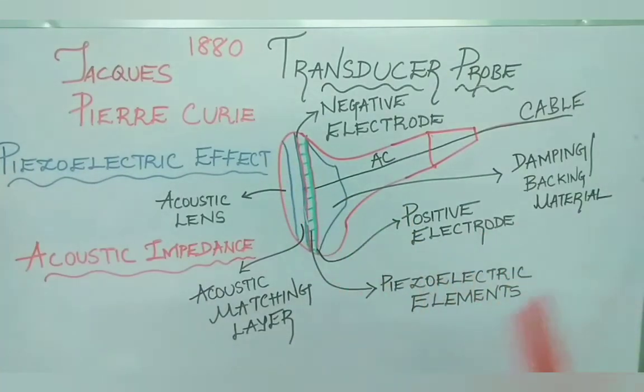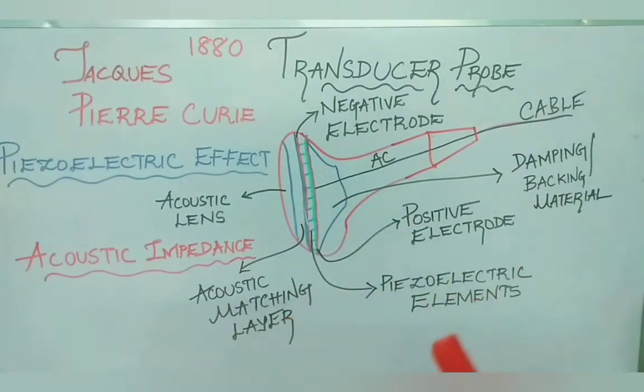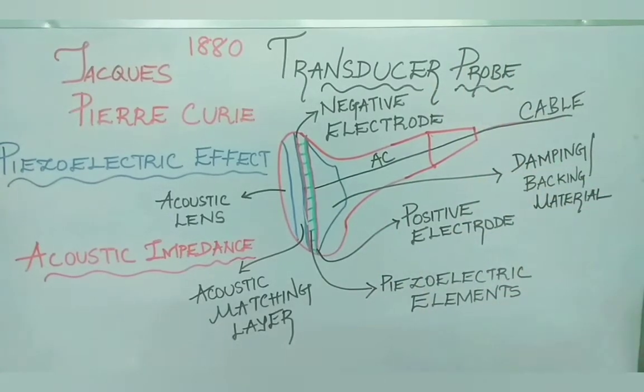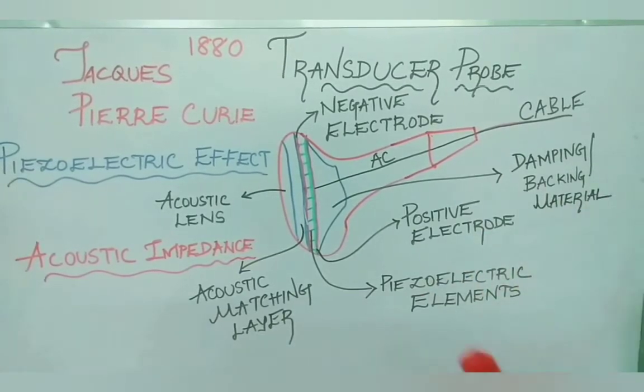Acoustic lens prevents the ultrasonic waves from spreading and focuses them to improve resolution. Acoustic matching layer provides the required acoustic impedance gradient for the acoustic energy or sound waves to smoothly penetrate the body tissue and for reflected acoustic waves to smoothly return to the transducer for detection.